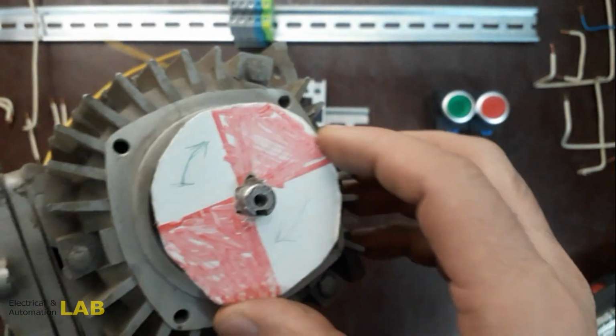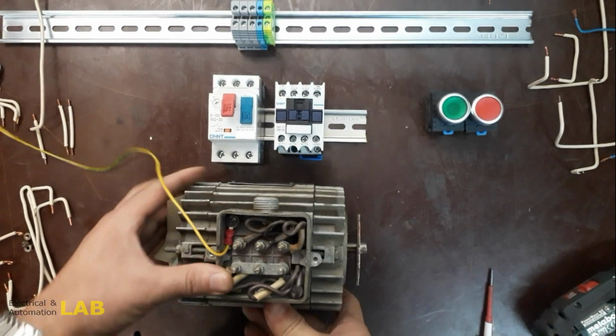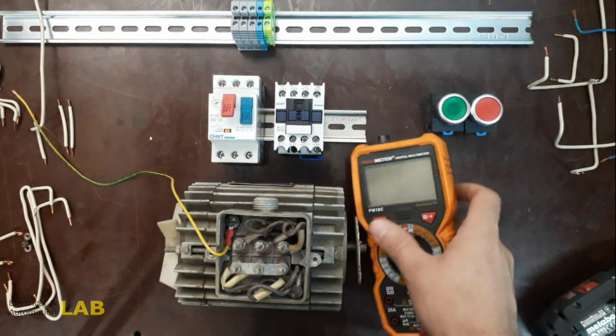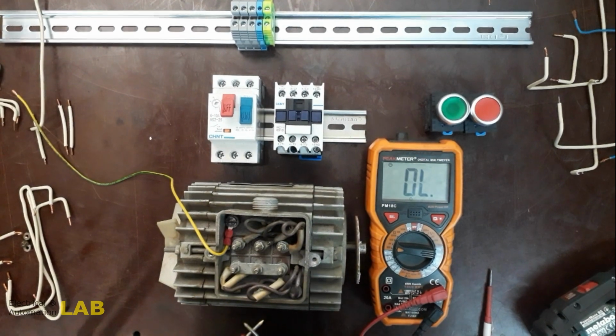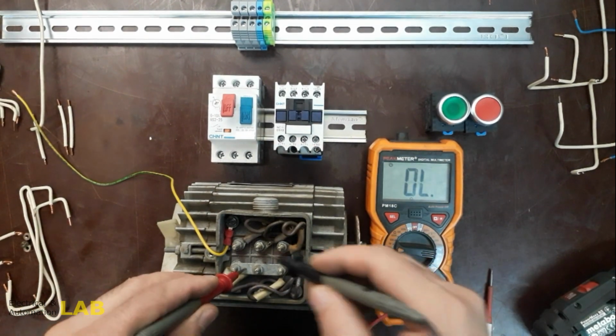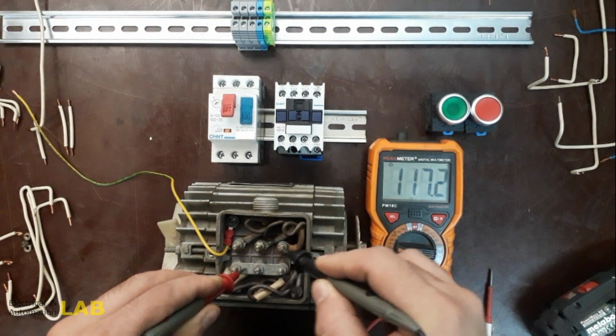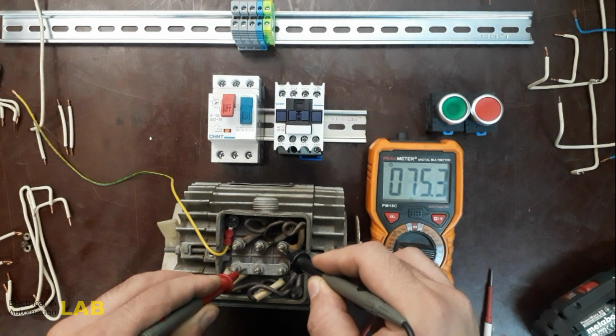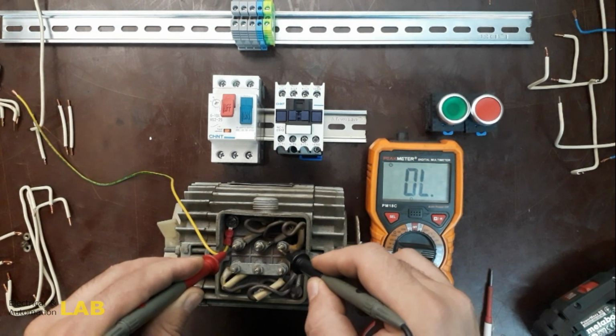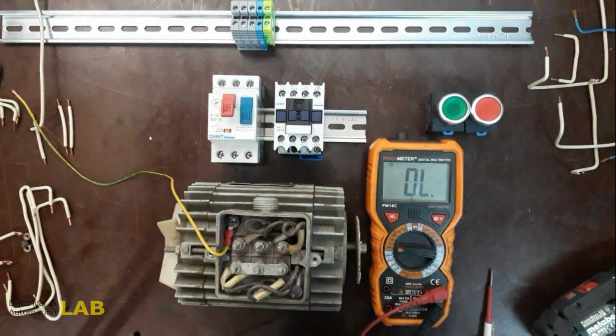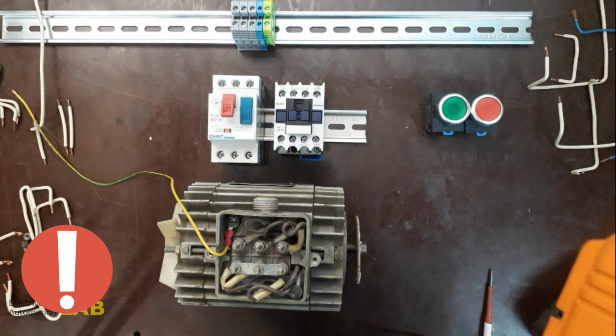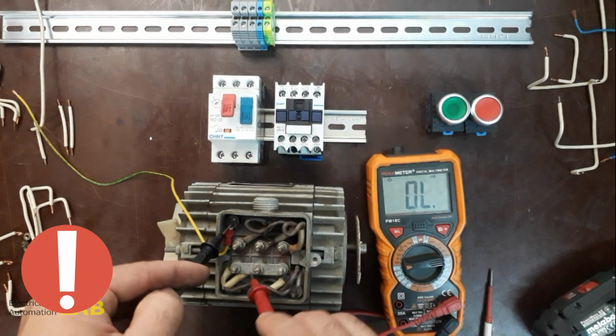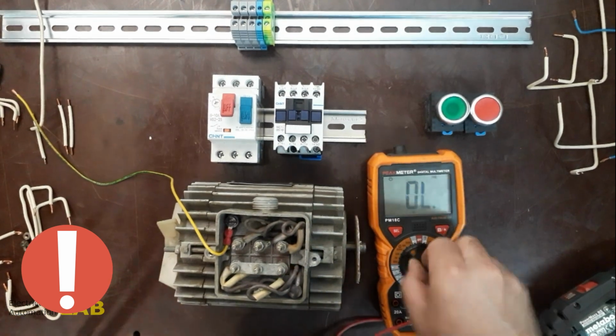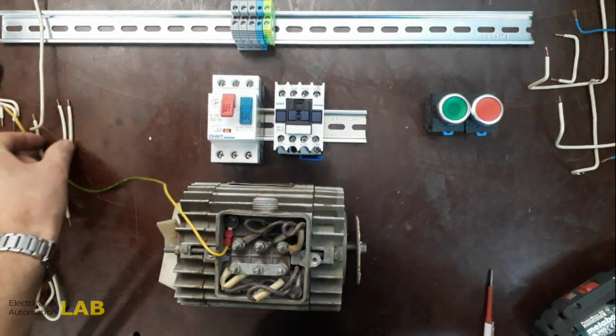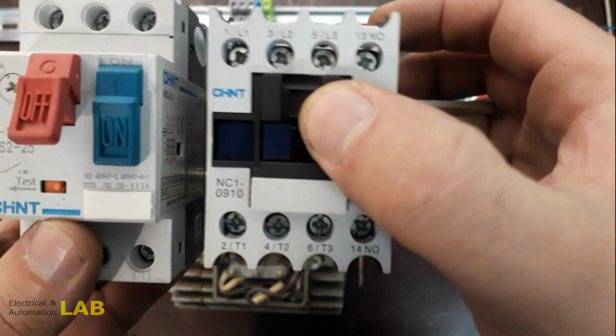We check the electric motor visually, try to twist it by hand, it should turn without third-party sounds. We take the multimeter and set it to continuity mode, check all the windings for resistance, we should not have a zero or a break in the winding. Do not forget to check with respect to the case. Checking the contactor and motor protection circuit breakers.